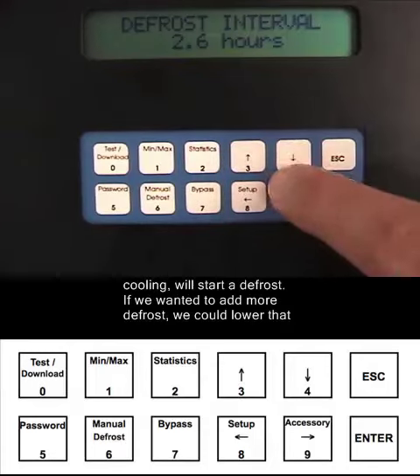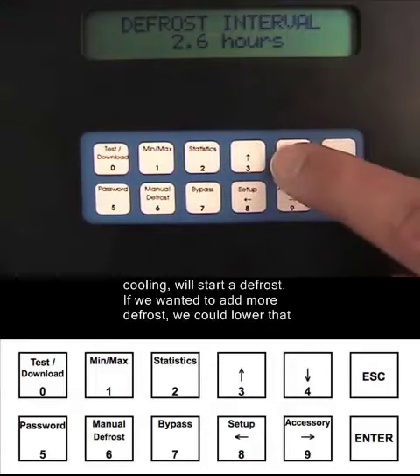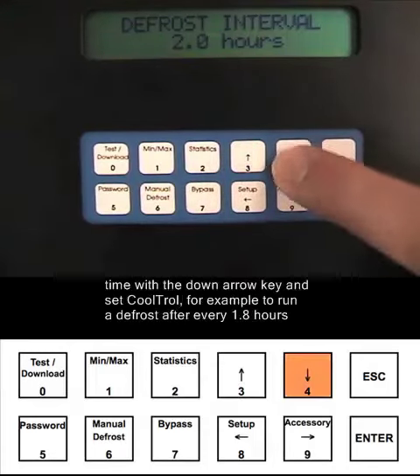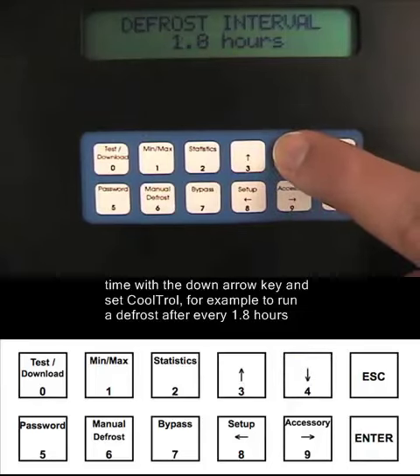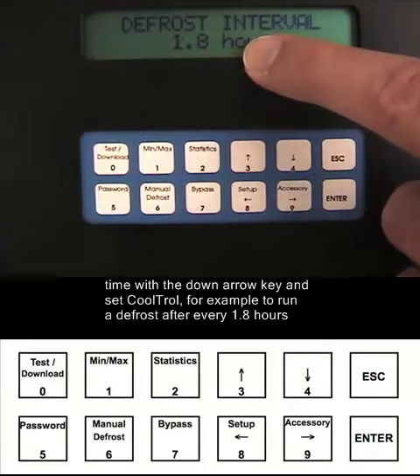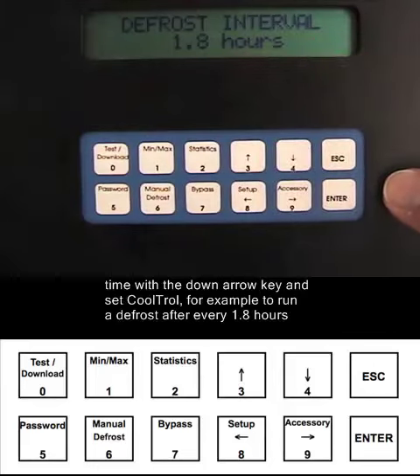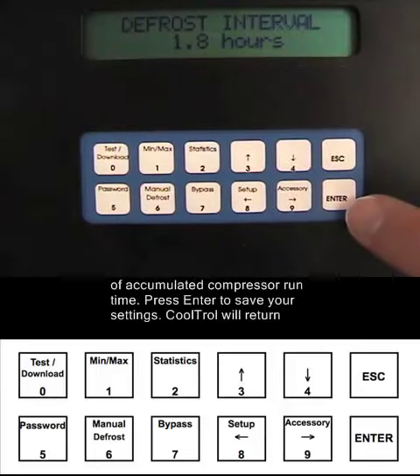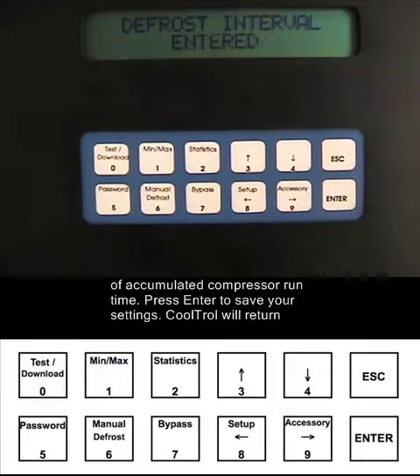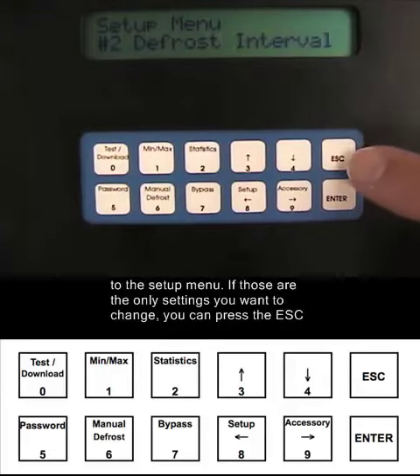will start a defrost. If we wanted to add more defrosts, we could lower that time with the down arrow key and set CoolTrol, for example, to run a defrost after every 1.8 hours of accumulated compressor runtime. And press enter to save your settings. And CoolTrol will return to the setup menu.